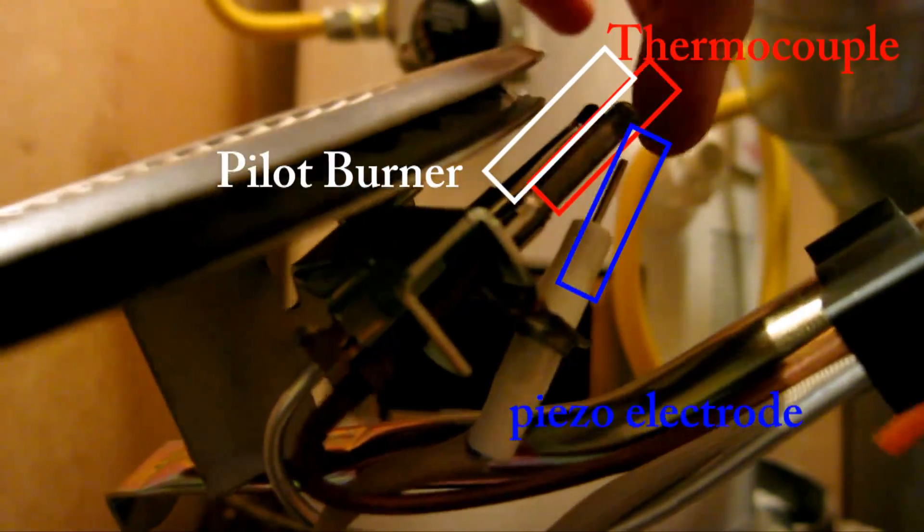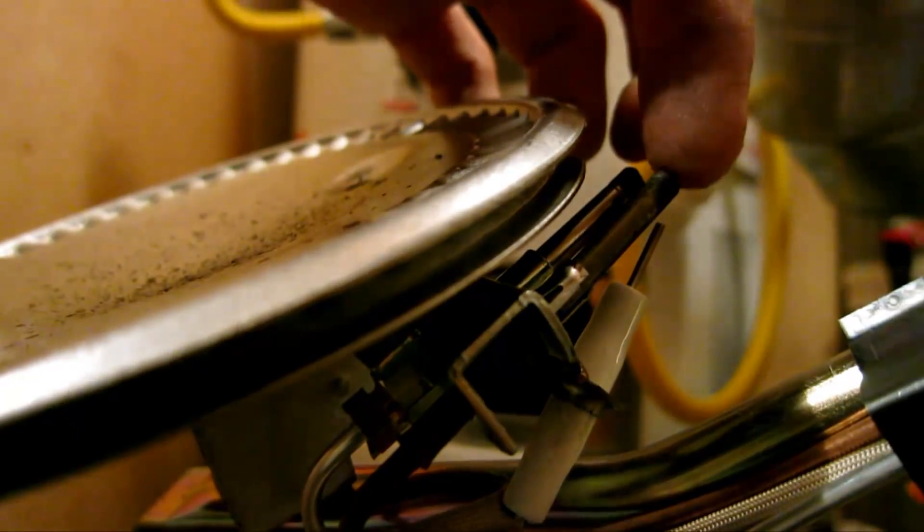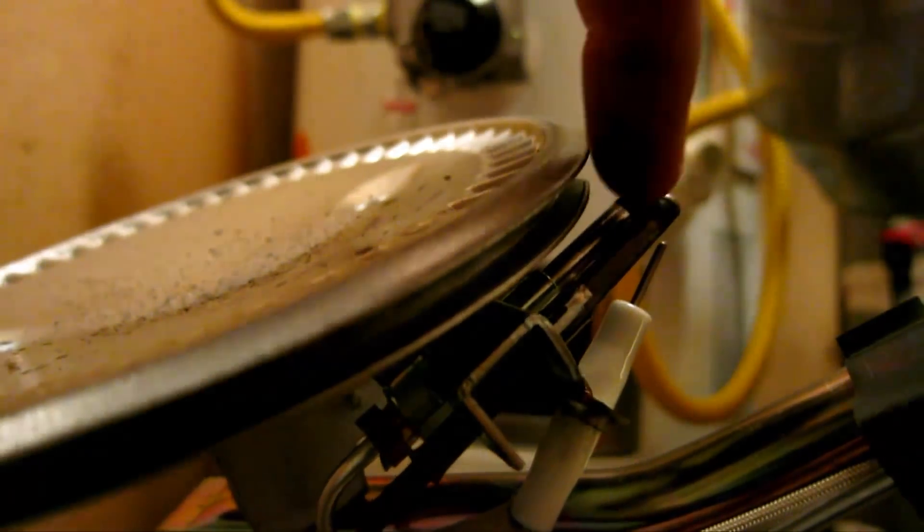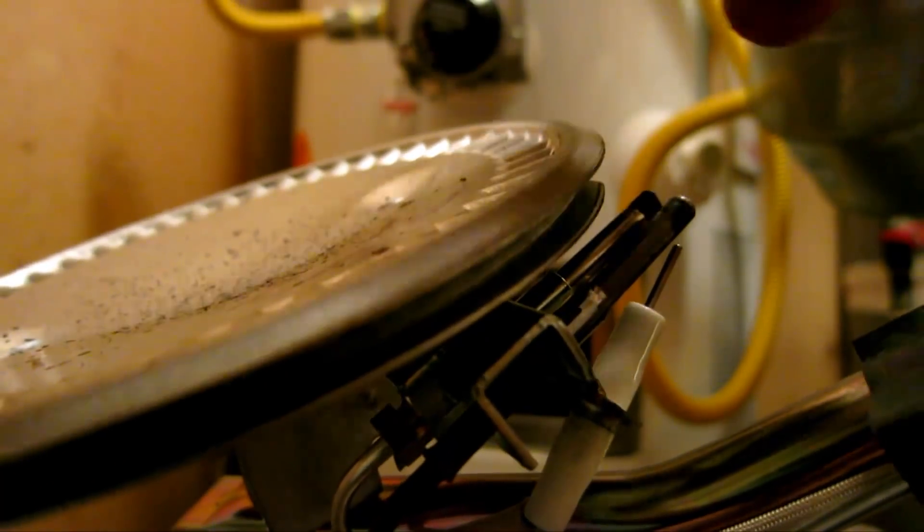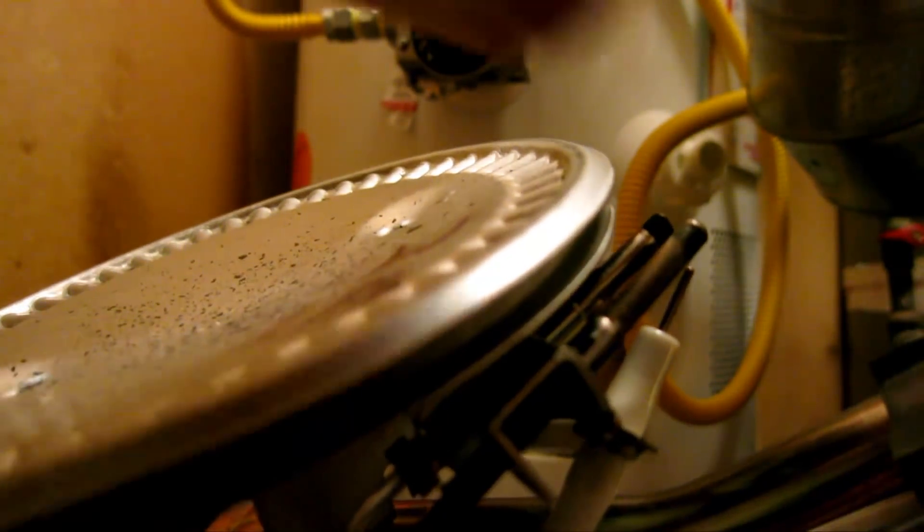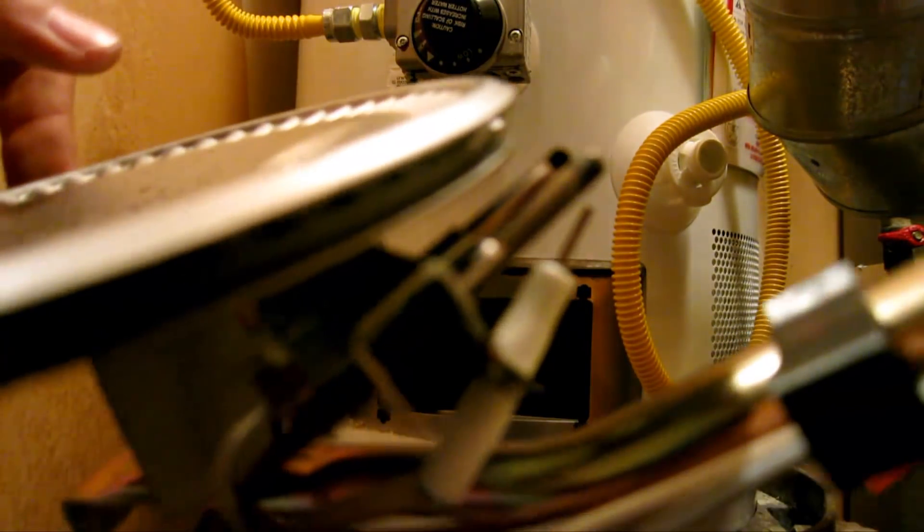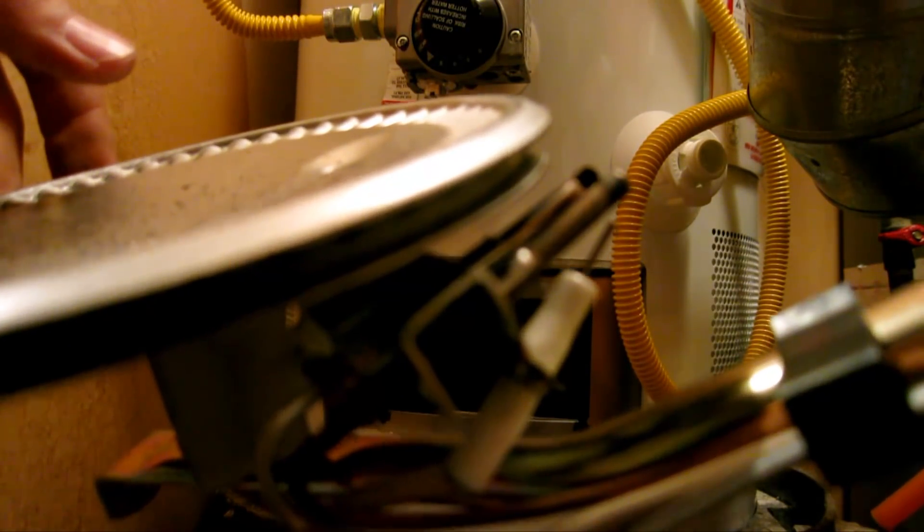So, here we go. That ignites it. Right here, that's the gas valve. And, right here, that's the thermocoupler. So, I was messing around with this, and the thermocoupler actually shifted down by, I would say, a quarter of an inch. So, maybe what happened was, when they were transporting this, it somehow got bumped down.